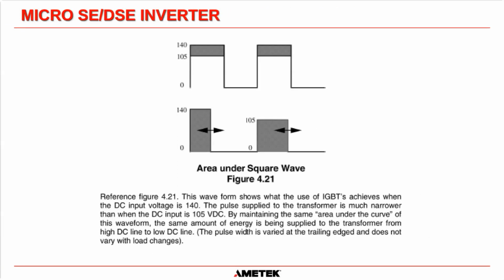Now, the only control that we have for the IGBTs in our ferroresonant inverters is we can change the area under the square wave. Basically, we can tell the IGBT when to turn off, okay? So you can see in both examples here that that's turning on at the same time and that's turning on at the same time. You can see here that that one's turning off at a different time from this one. This one here is still turning on at the same time, and the trailing edge there is different. What we're trying to say is we can move that trailing edge.